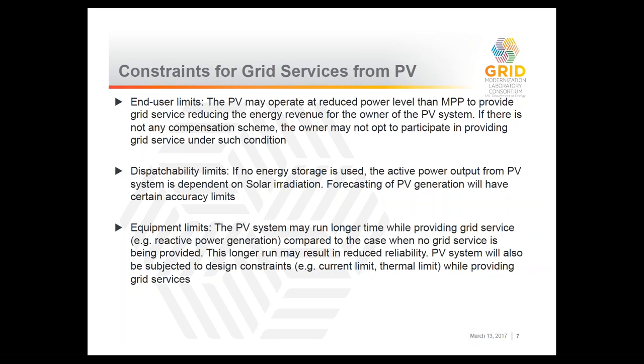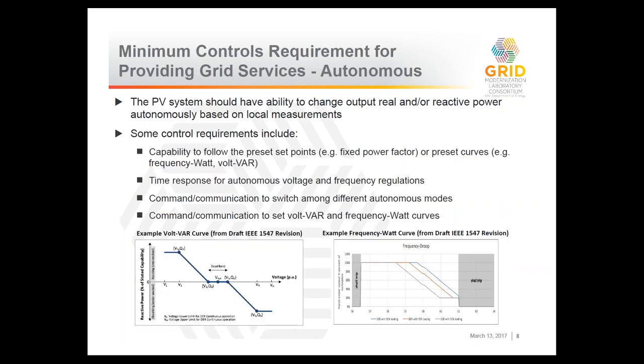There is also some dispatchability limit. As I mentioned, the dispatchability is as good as your forecasting, so there will be some forecasting accuracy limits there. And finally, there will be some equipment limits. For example, if you are running the PV system to provide voltage regulation for the whole day, you may have some impact on the reliability of the PV system or the lifetime of the PV inverter itself, because now you are reaching the current limit or the thermal limit of those systems. Just to tell you, we are not neglecting those. These are all part of this matrix that we are building for the PV and all other devices. So we are not just looking into the values, but also into the constraints and how we can address those constraints when you are comparing those devices.